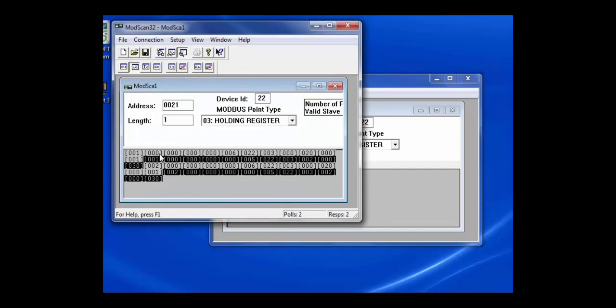So I have my transaction identifier 1, and then protocol identifier 00. 06 is the length, 22 is the unit ID, 3 is the read holding registers function code, 20 is the start. Remember, 40,021 minus 40,001, and 01, which is the number of memory address locations that we want. And everything in the MBAP header is reflected: unit ID, 3, 2, 2 number of data bytes coming back, and here's our 30, which is the value coming back right there. So it's pretty much like the read input registers, but I still wanted to go through it with you. All right, good.